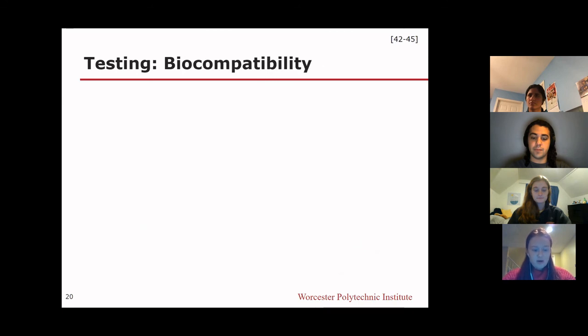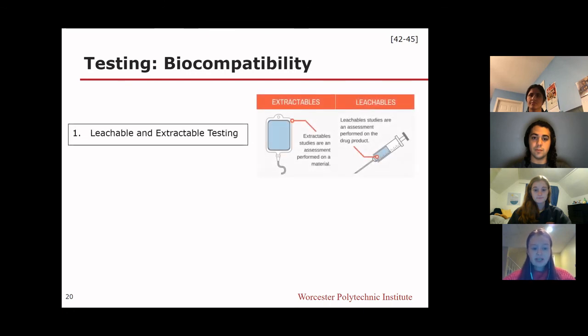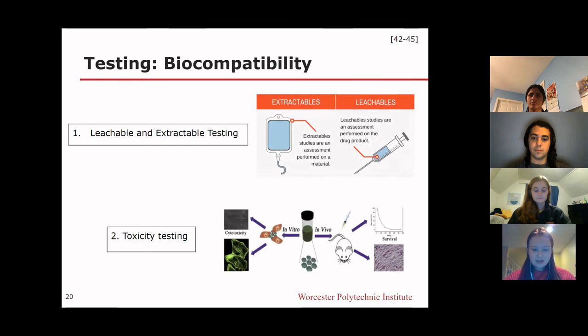We will also be performing multiple biocompatibility tests on the device. These will include a leachable and extractable test, which will involve placing the components and materials of the device in an extraction media to evaluate any of the leachable components that come out of the device for any cytotoxicity. We'll also be completing a systemic in vivo toxicity test, which will determine if any of the materials we will be using contain any chemicals that will cause negative effects after any prolonged exposure.